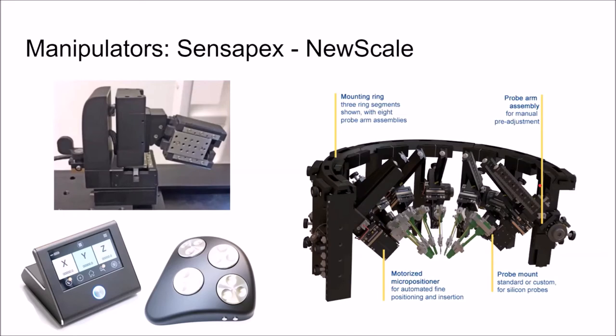So I go on. The display can be zeroed. And also each axis of movement can be disabled. So once you are inside the brain or inserting into the brain, you will only want to move in this dimension and not any other dimension. To be sure that this is not happening, you can disable each of these other axes. And now I heard you can also move each axis automatically with a certain speed. You can do this by controlling this touchpad, which was not previously possible, but now they updated their software, which is pretty nice. Now there's also other manipulators called New Scale. They did this kind of fancy setup if you want to use lots of different probes. The audio went a bit funny. Can you say again something setups?